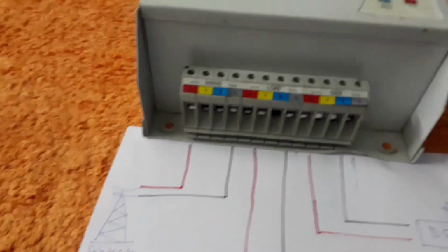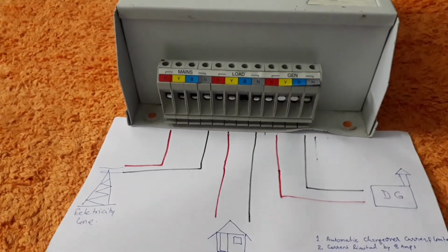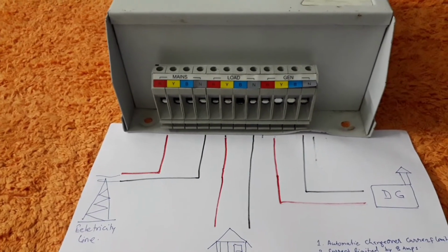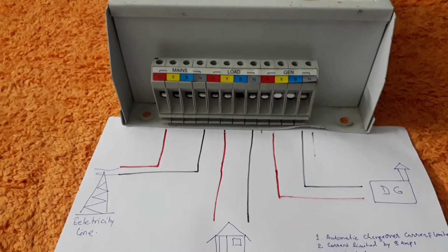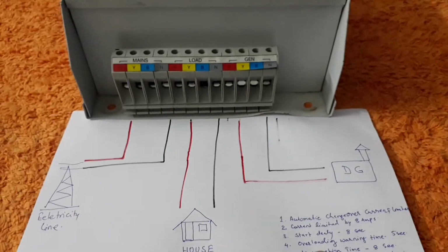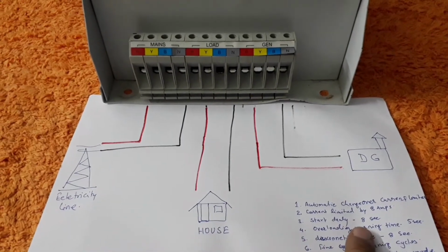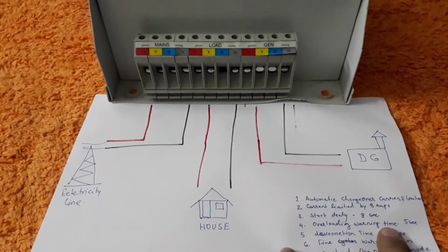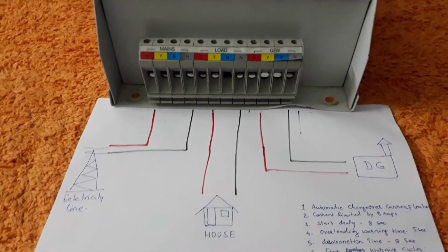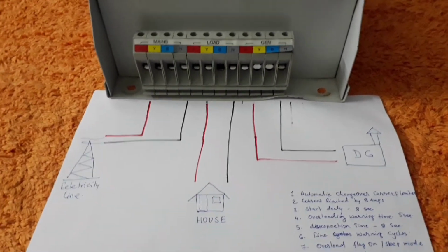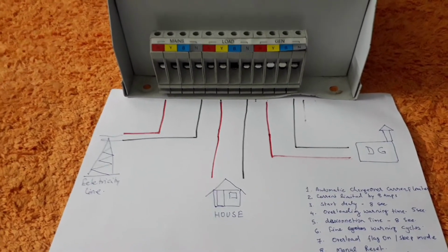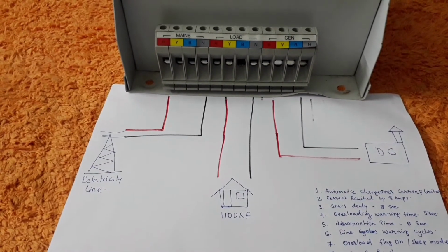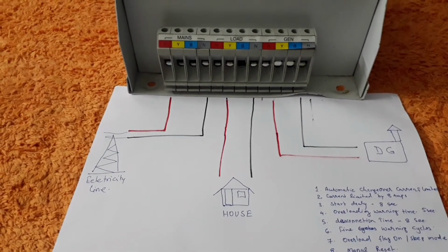And if all our loads are connected and ACCL finds the load is more than 8 ampere, it will automatically trip after 8 seconds. Within those 8 seconds, when the overloading condition happens, it will wait for 5 seconds. It will beep for 5 seconds, and that is the reason sometimes you can hear the beep from ACCL. It means you have a load of more than 8 ampere on the ACCL, and ACCL is giving you a warning to switch off some of the loads.